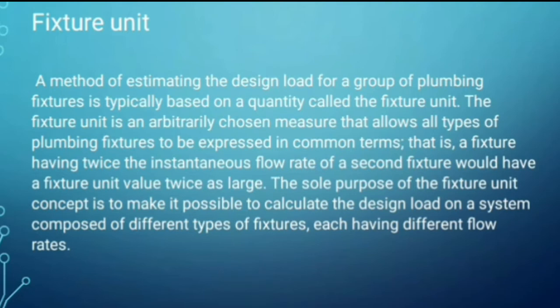The fixture unit is an arbitrarily chosen measure that allows all types of plumbing fixtures to be expressed in common terms. That is, a fixture having twice the instantaneous flow rate of a second fixture would have a fixture unit value twice as large.